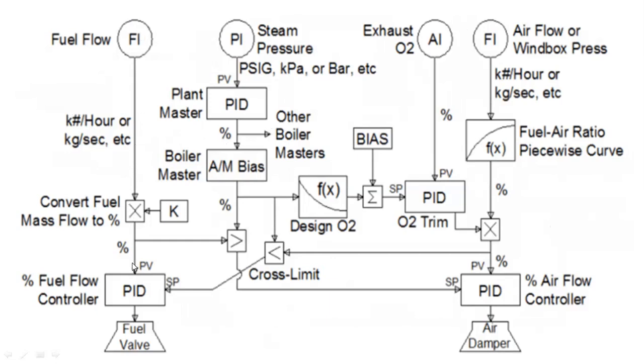The fuel flow line precisely specifies how many kg/s of fuel to give, and ultimately it is fed to a PID controller before going to the fuel valve. Similarly, for the air route, you sense oxygen from the exhaust and precisely determine the required airflow. A set point is established based on steam pressure and oxygen level, and this PID controller regulates the air damper to deliver a controlled airflow to the burner. These two — controlled fuel supply and controlled air supply — result in proper combustion for maximum combustion efficiency. That's all about the instrumentation and controls involved in combustion and furnaces.